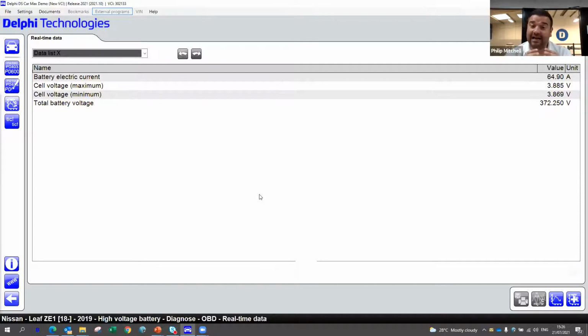Is the whole pack just aging, or is there maybe one or two modules that are suffering issues and the rest are all fairly close together? So if we had a 50 millivolt difference, we could have 90% of the modules only at 30 or 20, and then the last few are causing the problem - in which case it may then be worth moving into a diagnosis and repair stage by removing the battery and doing it that way.